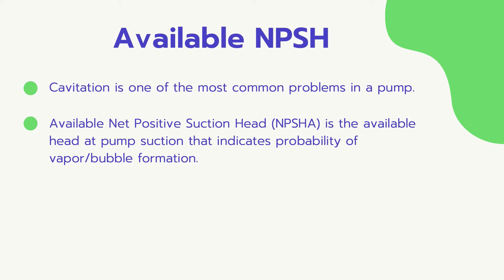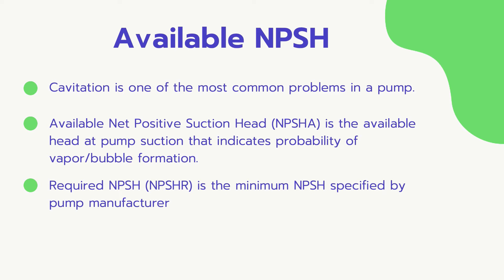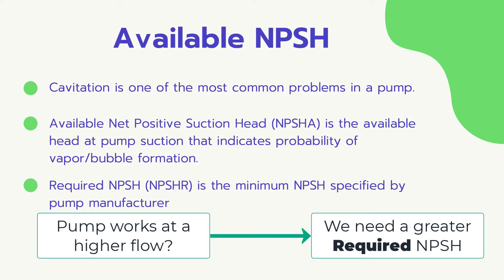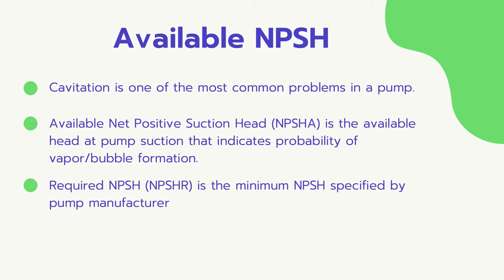But how much should the available net positive suction head be? Well, this mainly depends on the flow rate and the differential head of the pump. Each pump has its required NPSH, or NPSH-R. This is specified by the pump supplier and it depends on the operating conditions. So the NPSH-R at the rated flow is not the same as at 50% of the rated flow — at 50%, the NPSH-R would be smaller, which means less probability of cavitation.